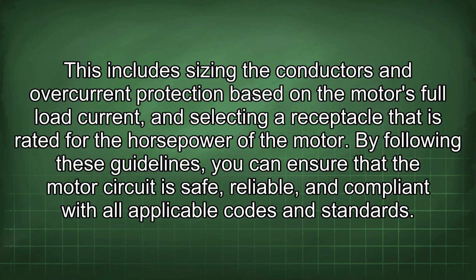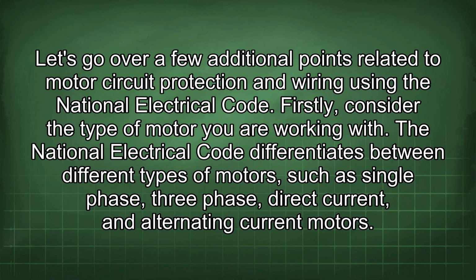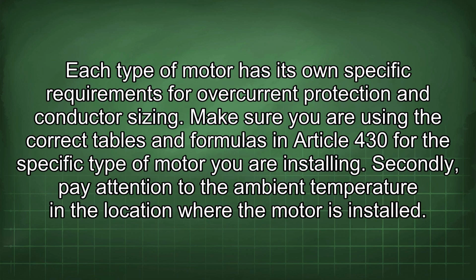Let's go over a few additional points related to motor circuit protection and wiring using the National Electrical Code. Firstly, consider the type of motor you are working with. The National Electrical Code differentiates between different types of motors such as single-phase, three-phase, direct current, and alternating current motors. Each type of motor has its own specific requirements for overcurrent protection and conductor sizing. Make sure you are using the correct tables and formulas in Article 430 for the specific type of motor you are installing.